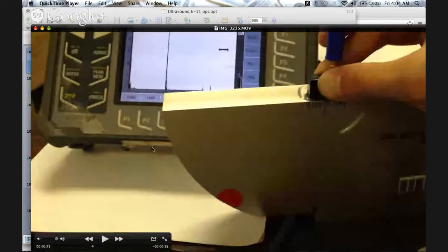That's why you see notches to your right. Your indication is coming here, bouncing, and because it's at an angle, it's going to bounce to the right. If I were to put this transducer further to the right, because this is a groove and not all the way through the material, I would lose these indications because the sound would keep going through my material. You have no reflector for it to come back up.